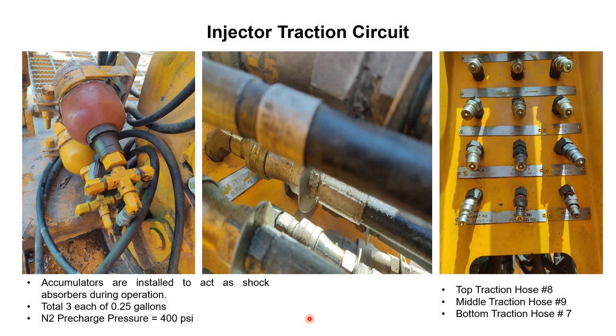There are a total of three accumulators, one accumulator for each circuit. We have three traction circuits: one for the upper cylinders, one for the middle, and one for the bottom pair of hydraulic cylinders. Each accumulator has a capacity of 0.25 gallons and the pre-charged nitrogen pressure is 400 psi. If the pressure is less than 400 psi, we have to recharge the accumulators using nitrogen kits.